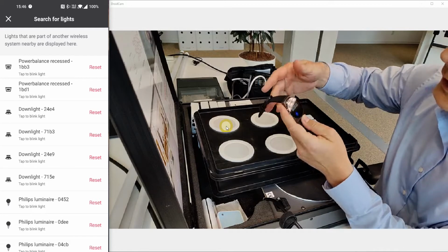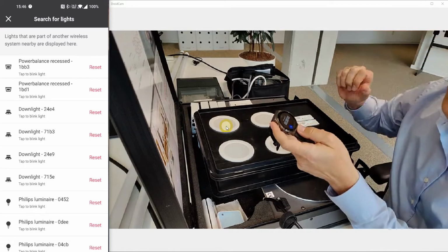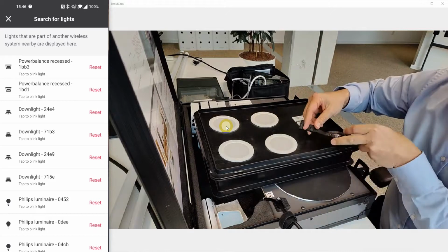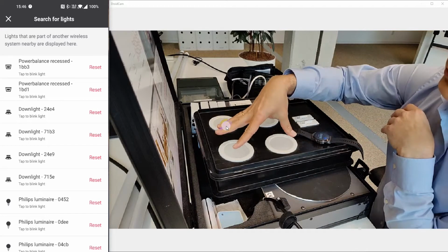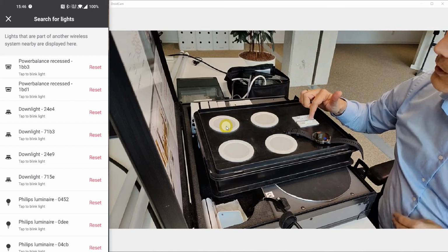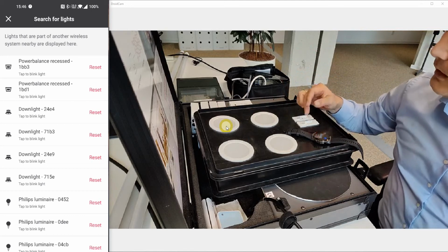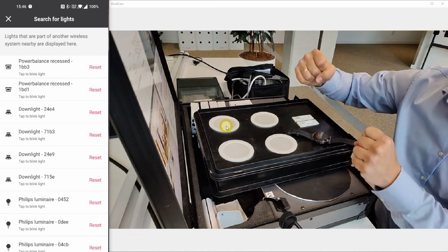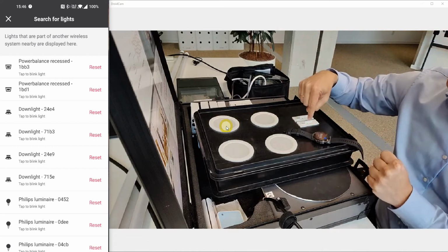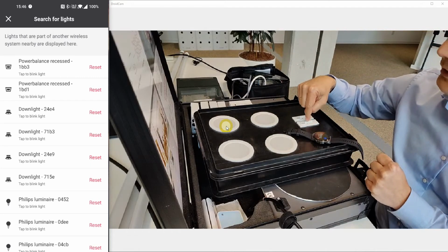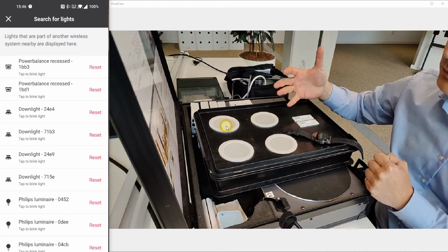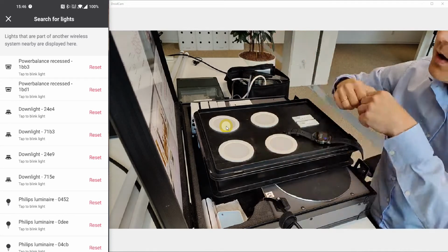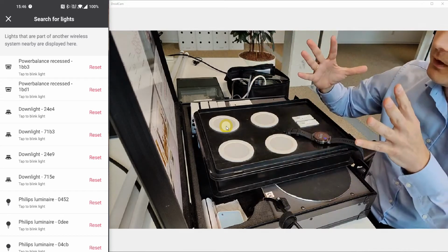Stopwatch. And let me do a 3-second power cycle. Sometimes it happens that when you try to do safe mode, especially with the luminaires with integrated sensors, that these sensors, even though there is no power, so I remove the power, somehow get power and they boot up very briefly.